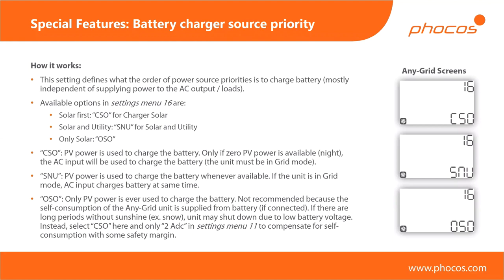Next, we have the battery charger source priority. There are only these two priority settings needed to operate efficiently. The first setting decides how your AC output is powered — how your loads are powered at any one time by solar, utility, battery, or a combination. The battery charger source priority is different: this is not how we power loads directly, but how we charge the battery. For example, you might not want to use the grid to charge the battery because that's just shuffling power around.